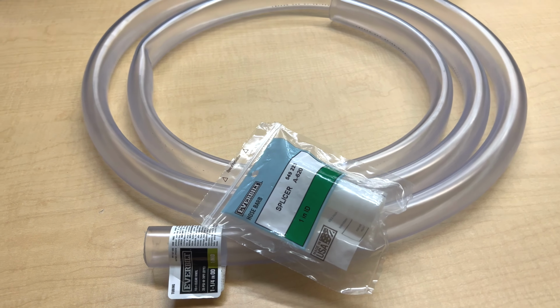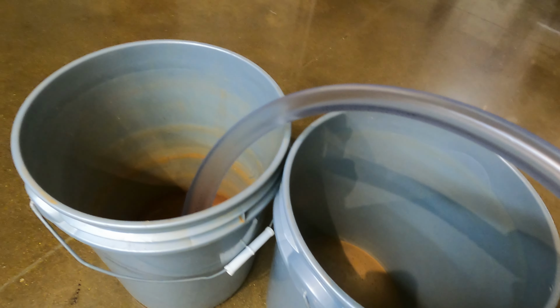So remove the condensate trap and its hose and install the hose assembly. The 8-foot-long clear acrylic hose is not only a sight glass, but it's also a better drain, and you can squeeze the hose quite a bit and that will circulate the descaler around inside the heat exchanger while it is soaking. After at least 2 hours, dispose of the descaler as per the manufacturer's guidelines.